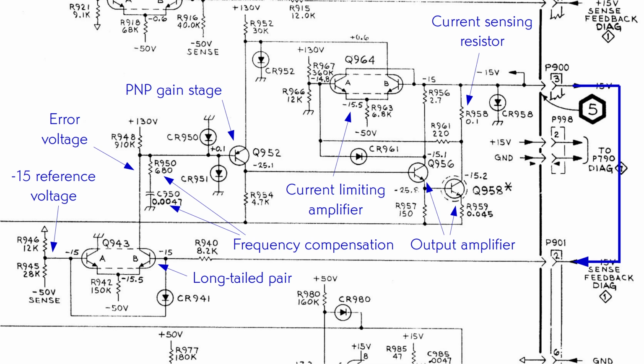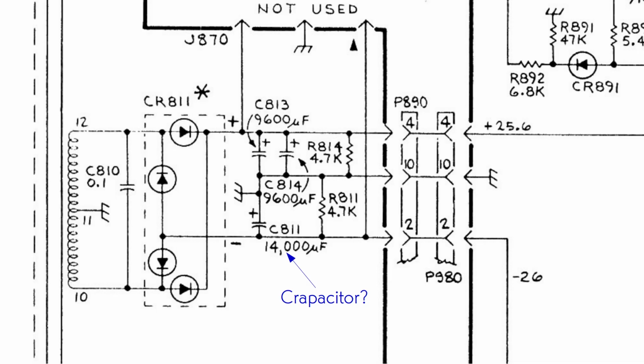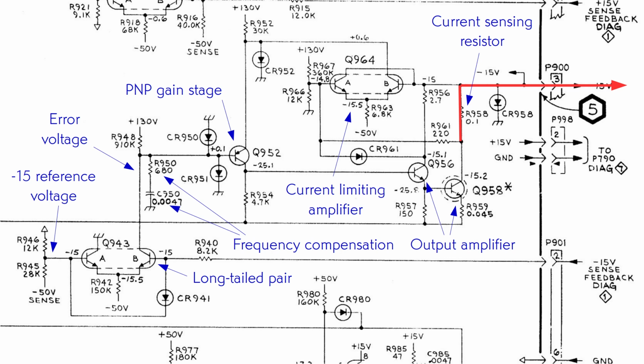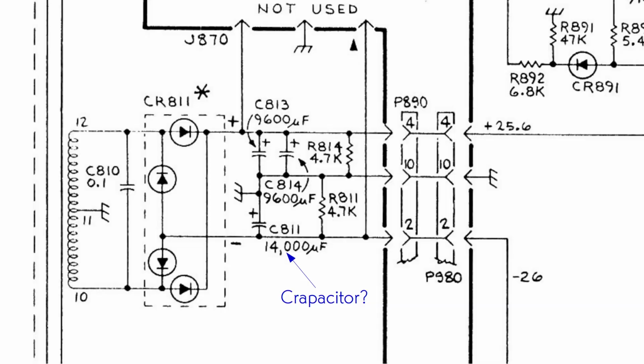There are only a few things really likely to be the culprit if this circuit isn't putting out the correct voltage. First, the filter capacitor hasn't aged gracefully and isn't filtering. Second, something else in the instrument is drawing overcurrent, causing the current limiting to drop the voltage—I don't think this is terribly likely, because if it were sucking down that much current I think I'd smell something overheating. Third, there's a corroded connection or a failed semiconductor in the regulator circuit—I don't think this is likely at all. My money's on the first possibility, a failed capacitor, C811.